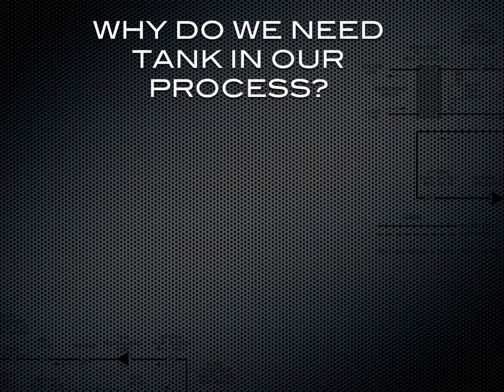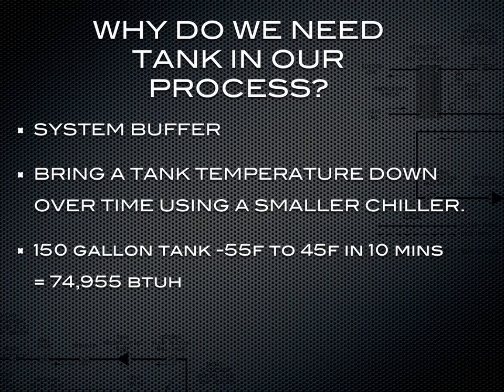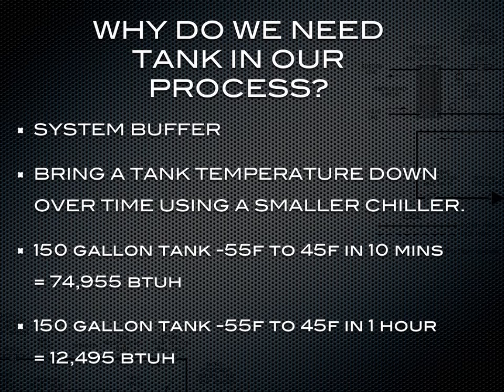Another reason to have a tank in your process is it can act as a system buffer. A system buffer is basically bringing a tank temperature down over time using a smaller chiller. For example, if you had a 150-gallon tank starting at 55°F, you could bring it down to 45°F in about 10 minutes with a 6-plus-ton chiller, or in about an hour with a 1-ton chiller. This is a good solution if you don't have a 6-ton chiller in your budget but you have a 1-ton.